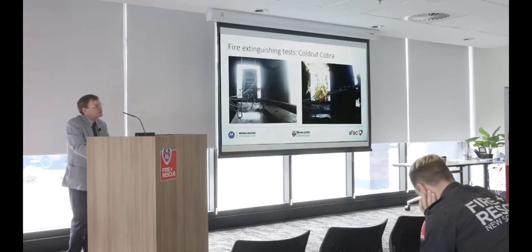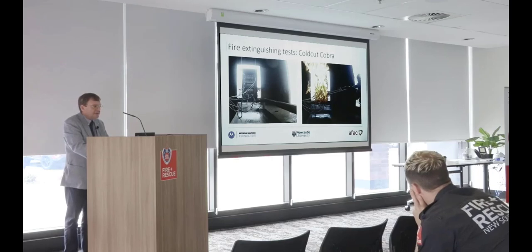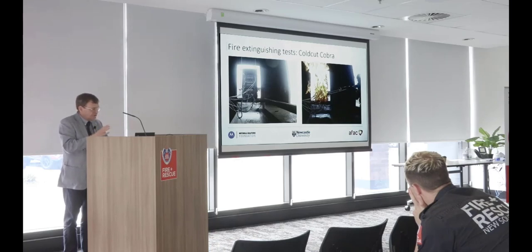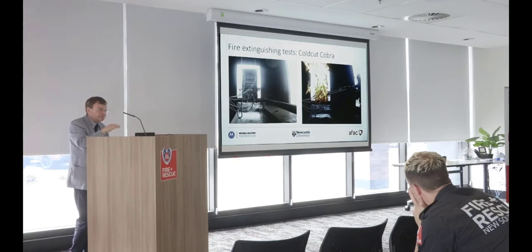So this is the cold cut cobra. It's a water lance with an abrasive in it, and the operator knew precisely where to position it to cut through the actual module that was in thermal runaway. So he knew what to do, and he could cut through both sides of the case and the module.